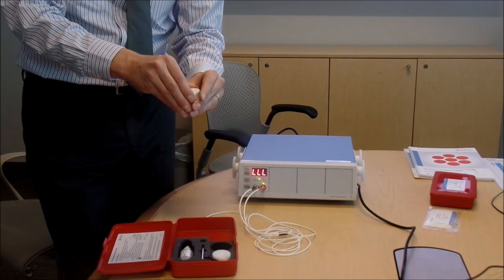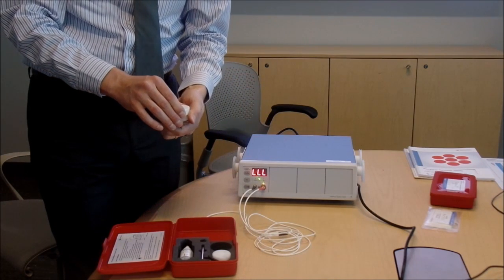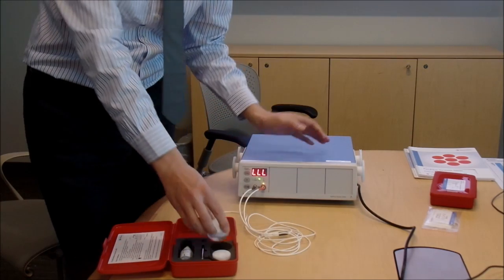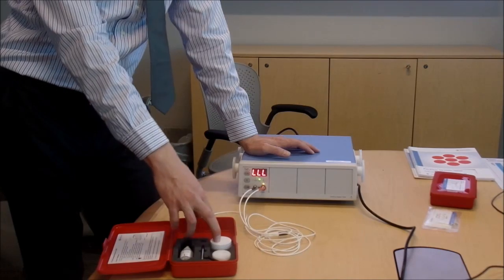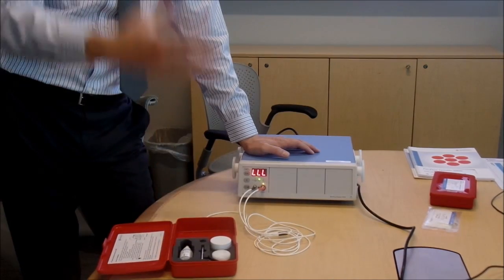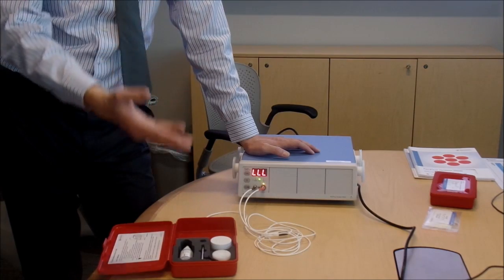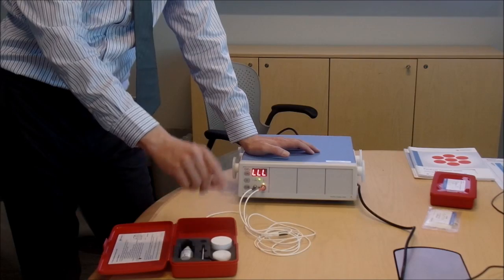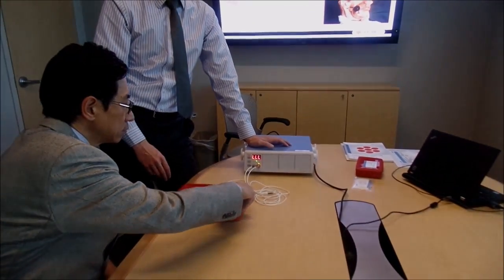Typically you don't really lose much fluid when you're performing the calibration. Oh, okay. The biggest problem in my experience with the calibration fluid would be if somebody forgets to put the cap on, and it just sits in open air for 3 days and maybe spills or evaporates. That might change things around. But if you do a calibration check like this and then immediately secure the lid back on, you're fine.